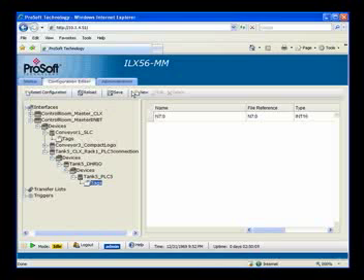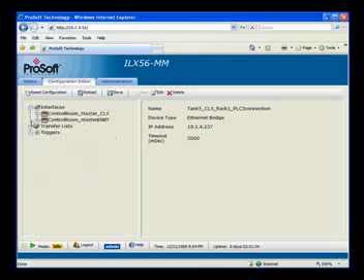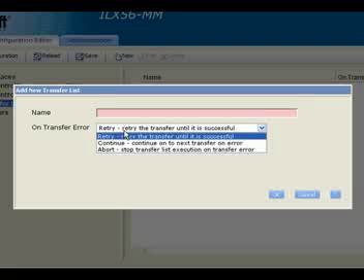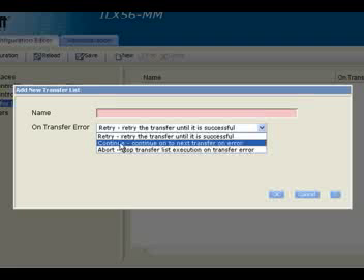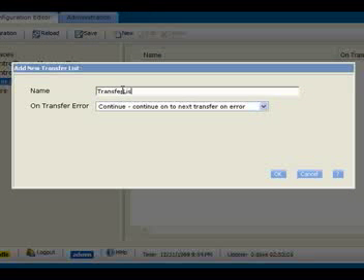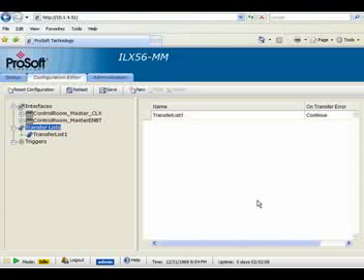Now that we've added our tags and devices, it's time to modify our transfer list. The transfer list defines the transactions within the module. I'll click on Transfer List, then New. We see the available options: retry the transfer until successful, continue on the next transfer, or abort — stop transfer list execution on transfer error. I'll go ahead and click Continue, give it the descriptive name 'Transfer List 1,' and click OK. Now Transfer List 1 is listed.